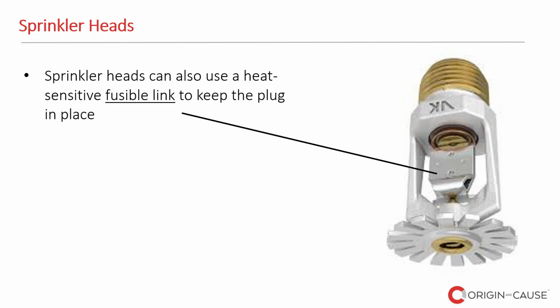This is what I was explaining before, that some of the sprinkler heads can have a fusible link. So no glass, it's just two pieces of metal that are joined by solder. And once it reaches a temperature, it goes off. These heads are typically more robust, and you can find them in high-rise residential or industrial applications. They're not as susceptible to being damaged. And if all the pieces are found during my investigation or the cleanup process and saved, then they do provide a much better insight as to what the root cause of the failure was.